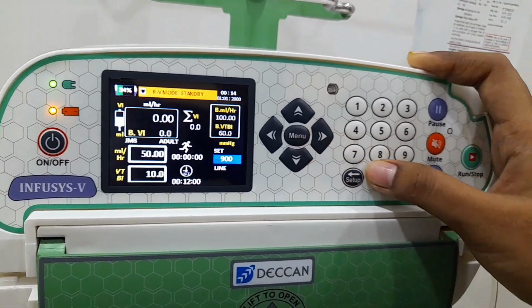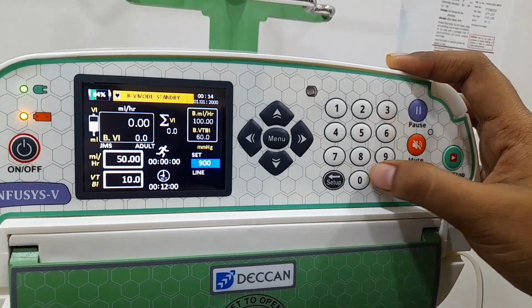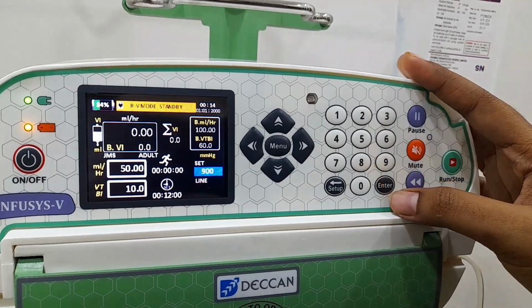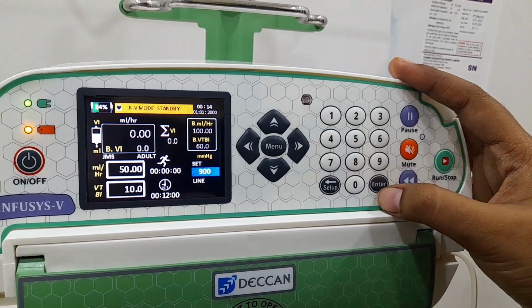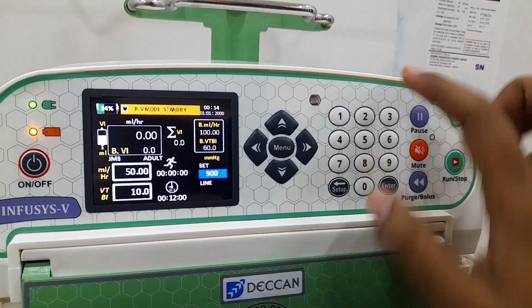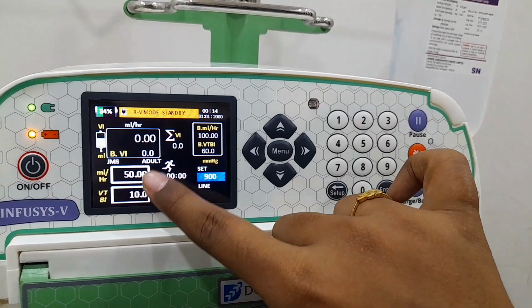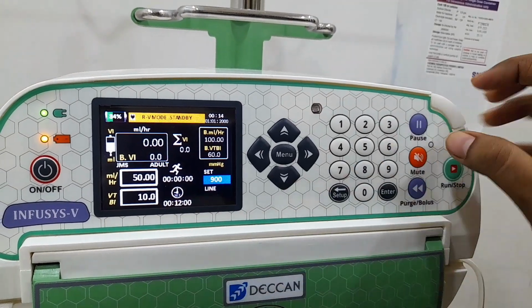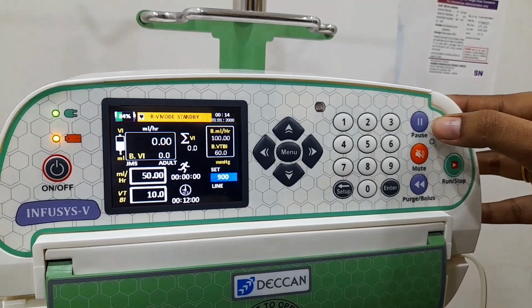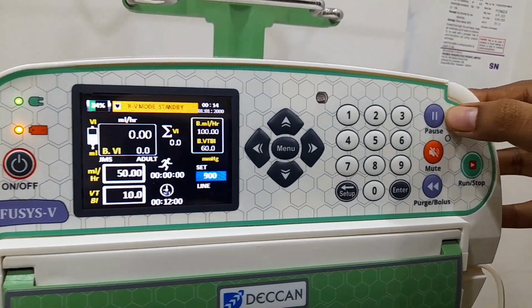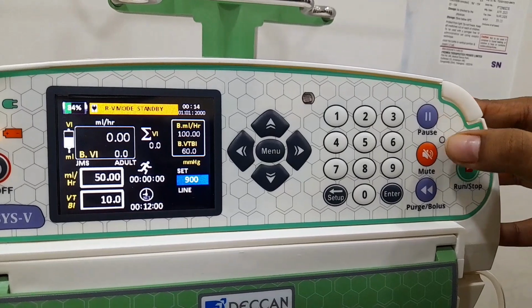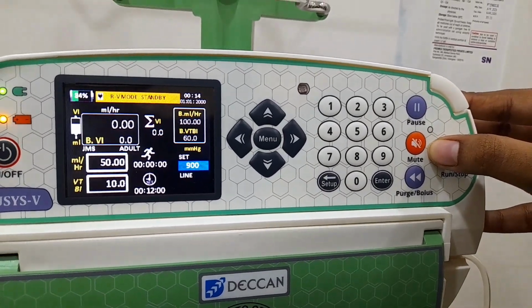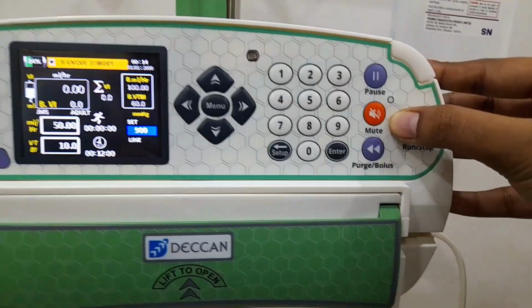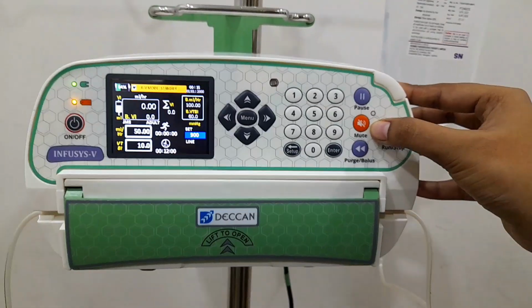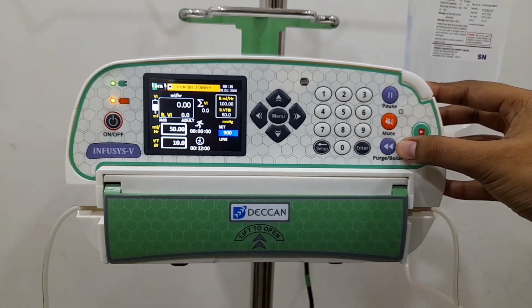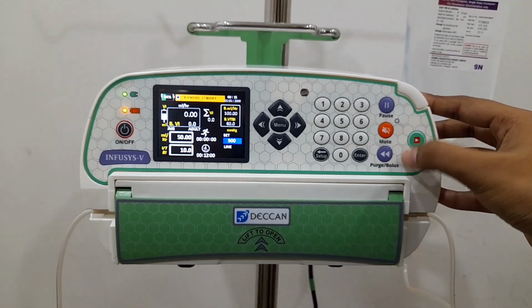And the numeric keys. The numeric keys are used to enter numeric values, and the enter key is used to set a rate, volume to be infused called VTBI, and time in all modes, and also the online bolus settings. And the pause key. The pause key is used to pause or resume the function while running. And the mute key. The mute key is used to mute or disable the alarms. Purge or bolus key. Long press the purge or bolus key for purge in standby and bolus while running. Double press for the online auto bolus setting.